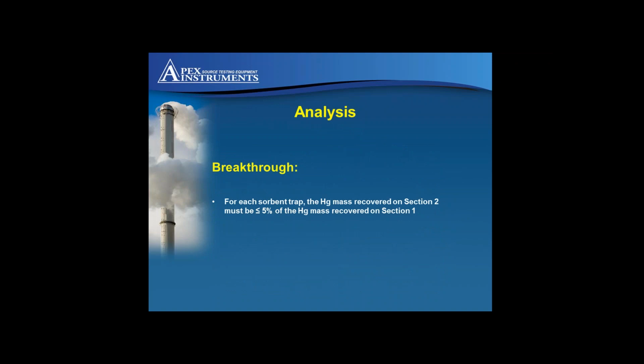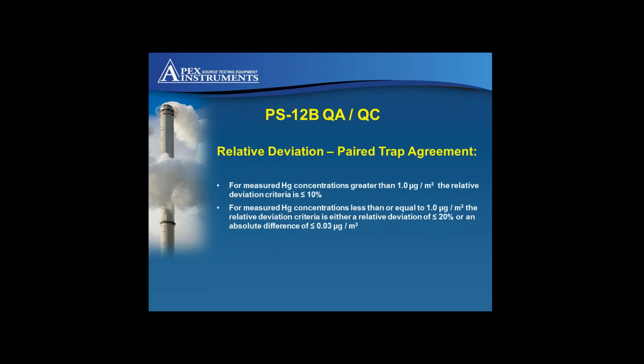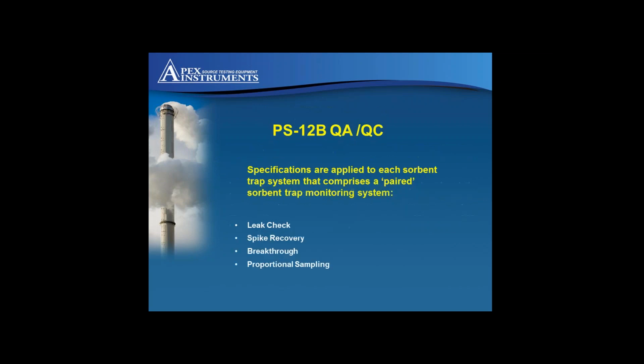From the standard, the analytical quality guidelines provide guidance on measurement, breakthrough tolerance levels, and spike recovery. Similarly, the tolerance levels. The standard also provides guidance on the relative deviation of the analytical result between the paired traps. So, for each measurement run, the paired traps must pass the pre- and post-leak check. They must comply with the breakthrough tolerance and the acceptable spike recovery levels, and proportional sampling throughout the test duration.